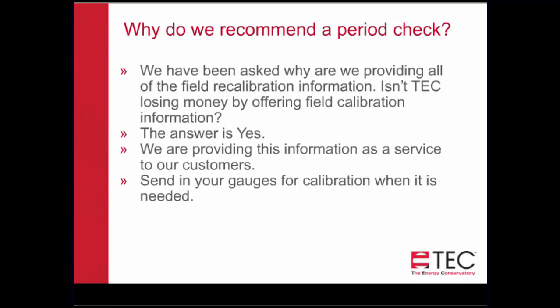So we encourage you to do your own calibration checks periodically. And it also helps you as long as you keep track of it. If you keep records of when you perform this calibration check, should you start to see a change where your instrument is moving out of calibration, you'll know that now's the time I need to do something with it. And if it's not moving, then you have a higher confidence in what you're doing out in the field, and in making sure that your instrument is working properly.